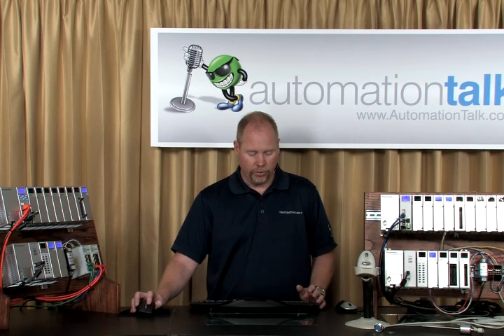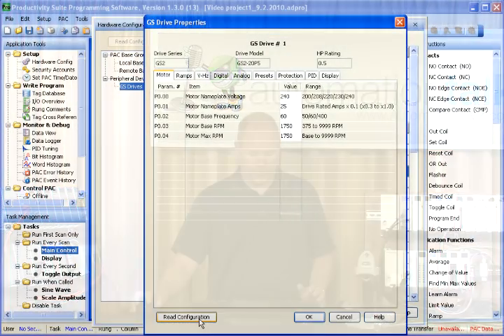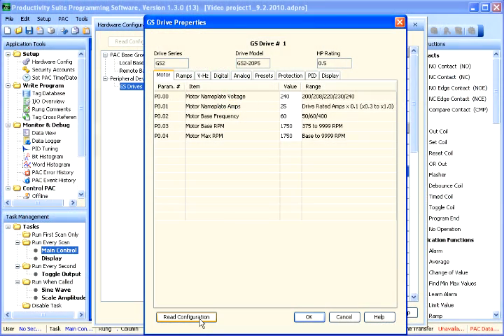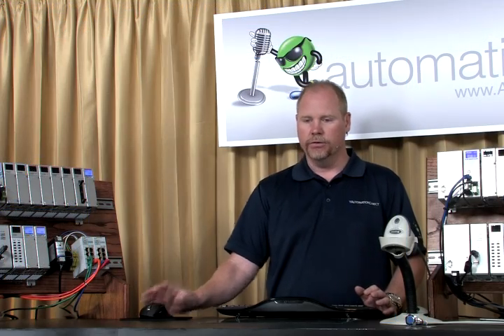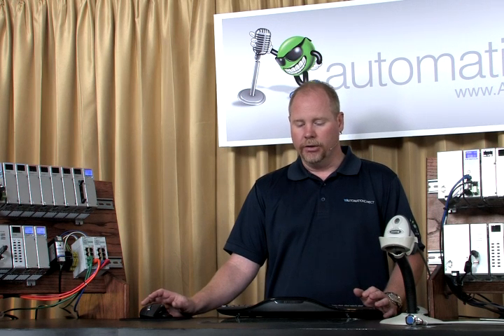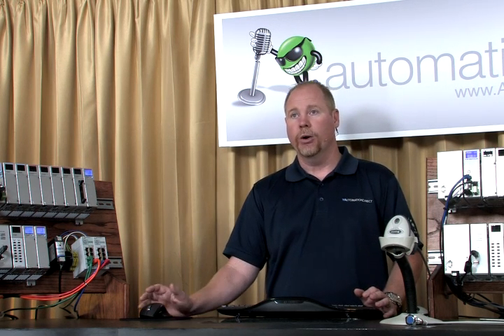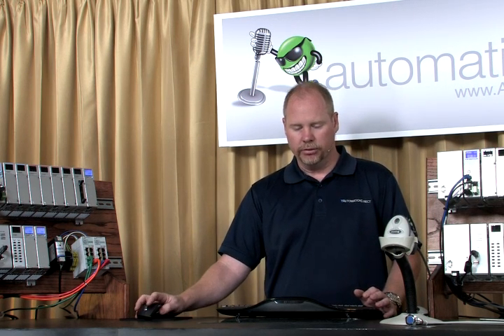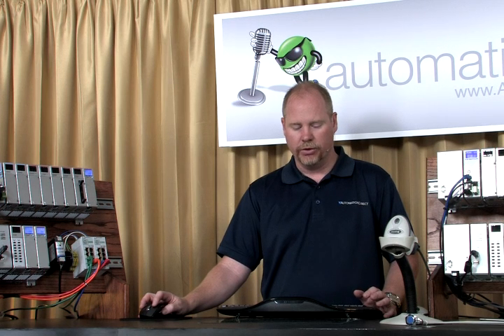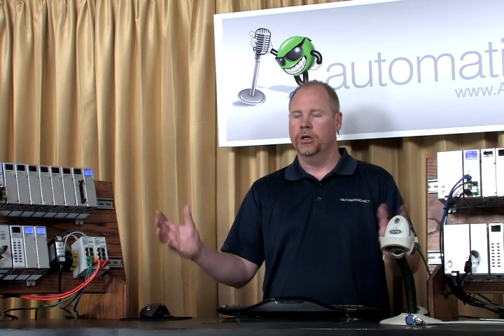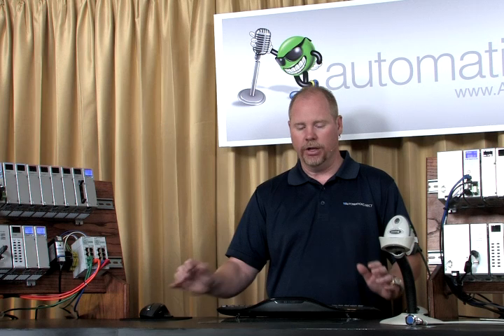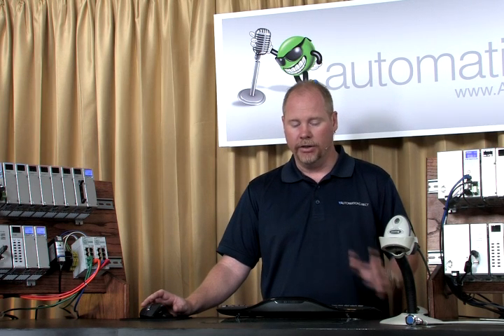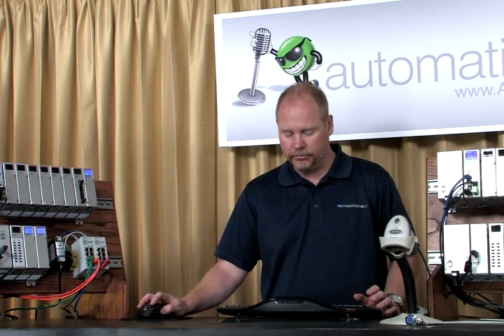As long as your system is up and running, you're online with the drive, you can hit read configuration and pull all the parameters out of the existing drive that you've got configured in your system. So this is very beneficial if you've got an existing system. You can tie your drive into the remote I.O. network, pull this screen up, hit read configuration, import all of your existing drive configuration, and then it's saved into your project.